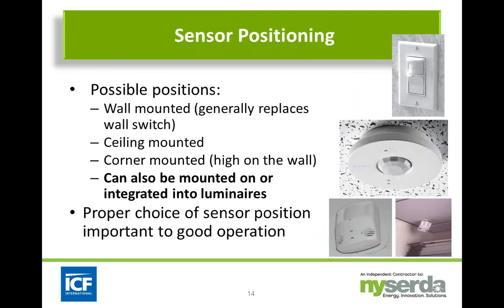Sensor positioning is actually a critical issue here. You want to make sure that they're positioned properly and commissioned properly for whatever your application is. But there's a couple of options that you have. You have wall-mounted sensors, which is probably the most common. Take an old single-pole toggle switch off the wall and replace it with a single-pole wall-mounted occupancy sensor, and most often they're going to be vacancy sensors.